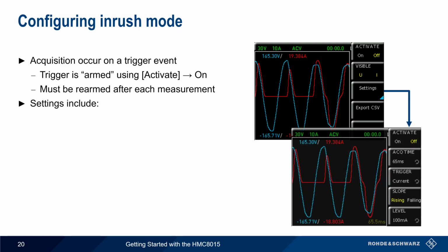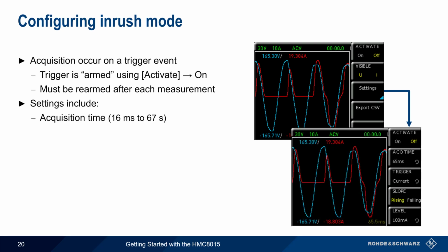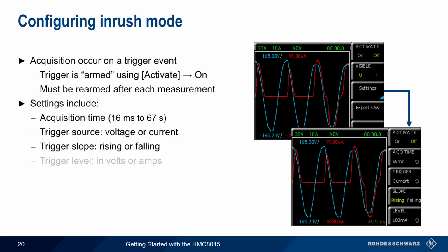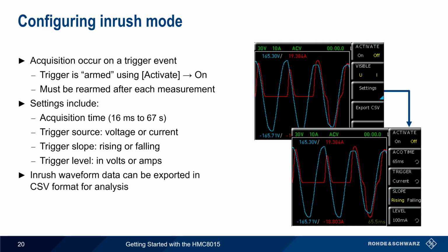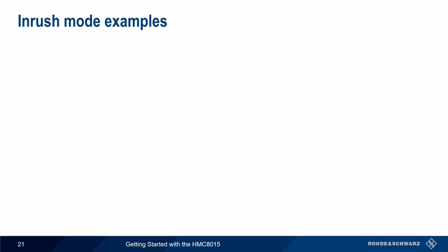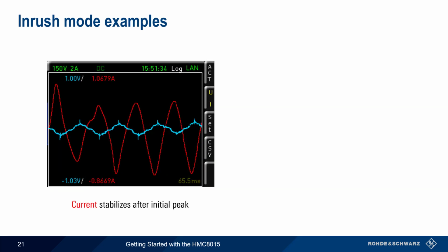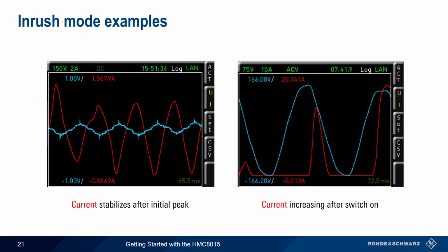Settings include the acquisition time from 16 milliseconds to 67 seconds, the trigger source, which can be voltage or current, but is usually current, the trigger slope, rising or falling, and the trigger level in either volts or amps. Note that the Inrush waveform data can also be exported in CSV format. Here are a couple of examples of Inrush mode. In the first example, we see that the current has an initial peak of about 1 amp before stabilizing at a lower level. Whereas in the second example, the device under test draws more current with each voltage cycle.